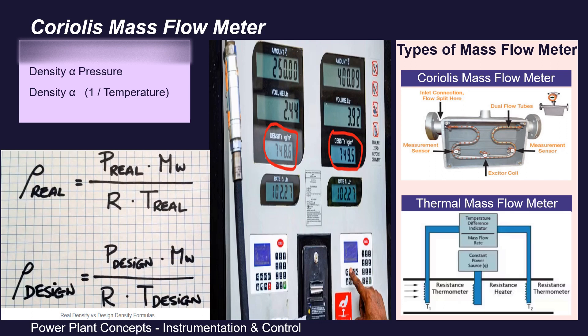Suppose you are purchasing water or gas from somewhere to run your power plant, or selling your steam to a refinery, desalination plant, or deaerating system. There is a requirement to meter it accurately. Even to check your boiler efficiency, you may have to precisely measure inputs consumed like water and outputs produced like steam. In all these cases, volumetric flow measurement will be misleading as the actual quantity will differ if the pressure and temperature conditions vary.